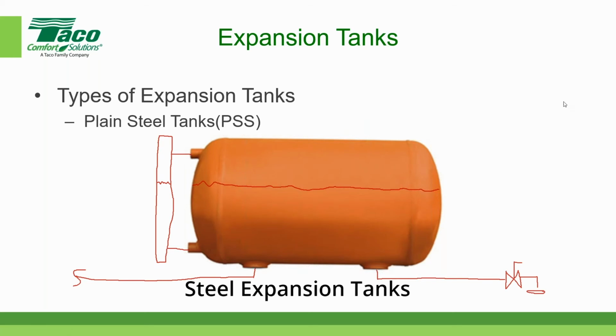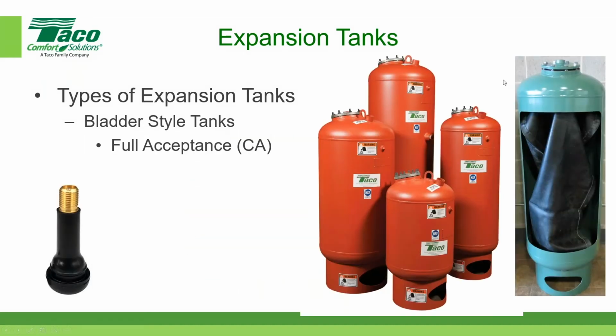Let's see if I can erase these lines here. The next category is called a bladder style tank, and the first one in the bladder style tank is called a full acceptance. And over here on the right, I have a cutaway of a bladder style tank. And if you'll notice, it's made up of two major components. There's the steel container. I'm pointing to that steel container on the right. That's the green device. And then physically inside the tank is the rubber bladder. Sometimes people refer to it as a balloon. And in terms of where the water and air goes, the water, when it expands, goes inside the bladder. And we do have to have air that we add to the void space. So I'm pointing to the void space now. That's the space between the bladder and the steel container. And that's where we add compressed air.